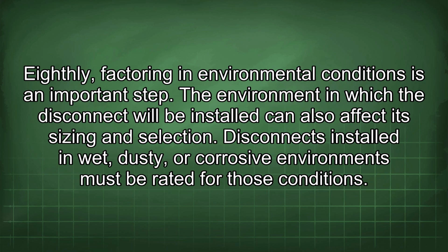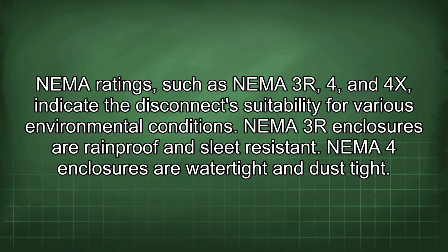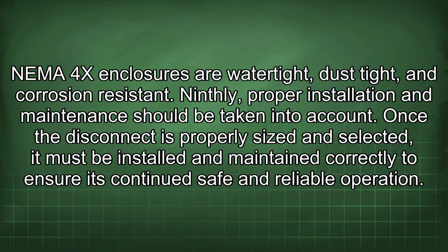Eighthly, factoring in environmental conditions is an important step. The environment in which the disconnect will be installed can also affect its sizing and selection. Disconnects installed in wet, dusty, or corrosive environments must be rated for those conditions. NEMA ratings such as NEMA 3R, 4, and 4X indicate the disconnect suitability for various environmental conditions. NEMA 3R enclosures are rainproof and sleet resistant. NEMA 4 enclosures are watertight and dust-tight. NEMA 4X enclosures are watertight, dust-tight, and corrosion resistant.